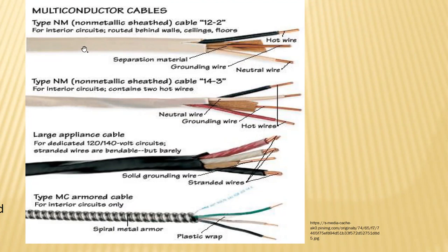Sometimes you're going to have the whole house done in timber, and maybe some of the inside walls are going to be added and they will be made out of steel because of a later addition or whatnot. If that's the case, if you really, really want to mount it to the frame, then you're going to have to screw in a timber stud to the metallic frame, and then you can mount that on the wood timber frame, on the 2x4. Can you run that in the metallic conduit? Yes, you can. So you can't run surface on metallic frame unless you run a conduit or a pipe, and you can put it in the pipe and run it that way.